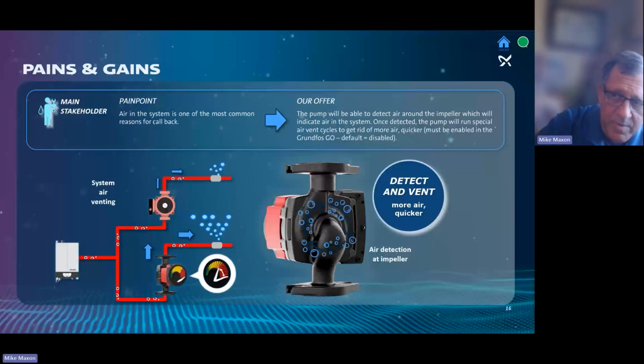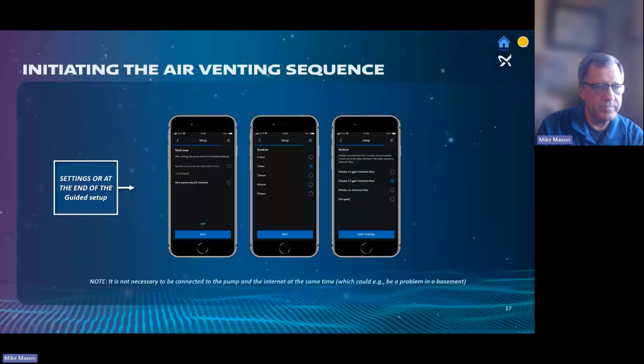Okay, so we talked about the venting of the pump, getting the air out of the rotor can, which then goes into the system. We also have, for heating pumps, getting the air out of the entire system. Once you set up the pump, here's the end of the guided setup. The last question I'll ask is, do you want to go through a system air vent? At this point, you could say, yeah, I want to do the system air vent, and you can tell it how long you want to do the air venting and what your minimum flow would be.